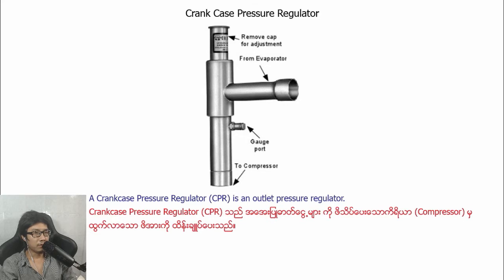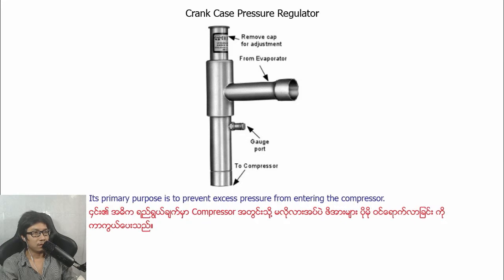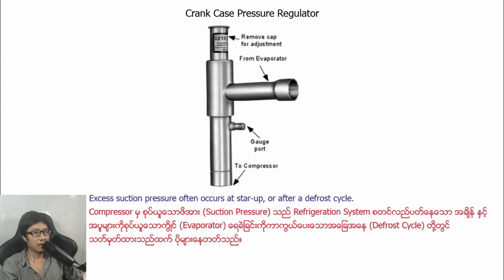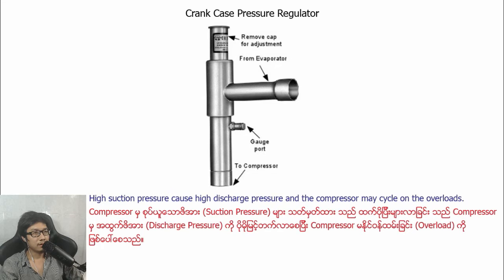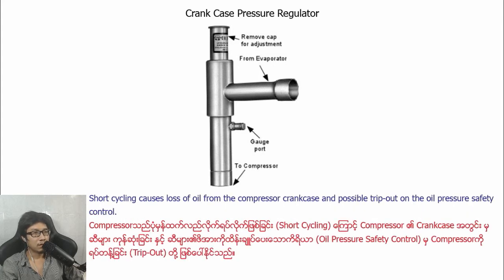A crankcase pressure regulator (CPR) is an outlet pressure regulator. Its primary purpose is to prevent excess pressure from entering the compressor. Excess suction pressure often occurs at startup or after a defrost cycle. High suction pressure causes high discharge pressure, and the compressor may run on overload. Short cycling causes loss of oil from the compressor crankcase and possible trip out on the pressure safety control.